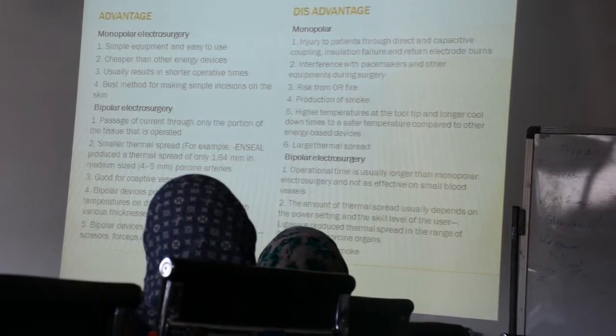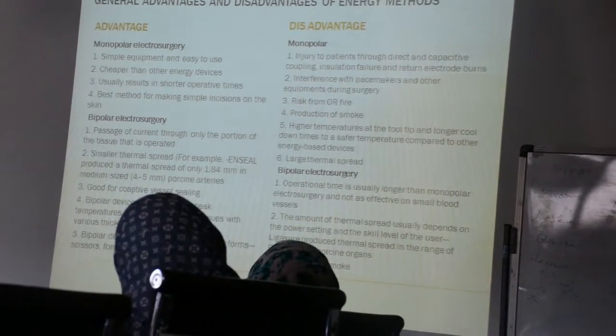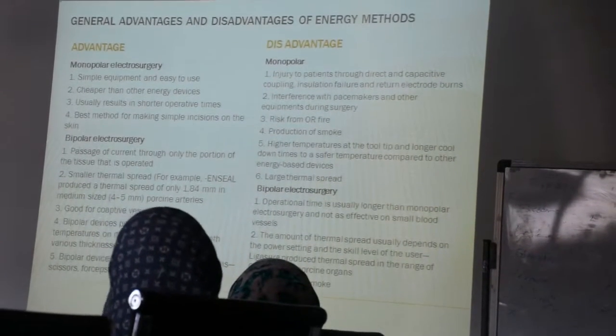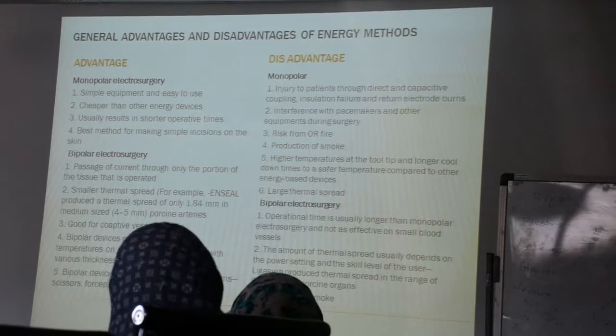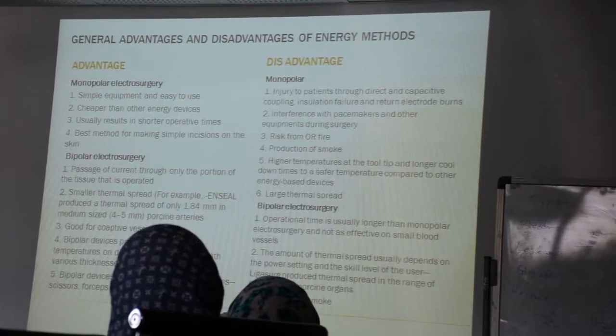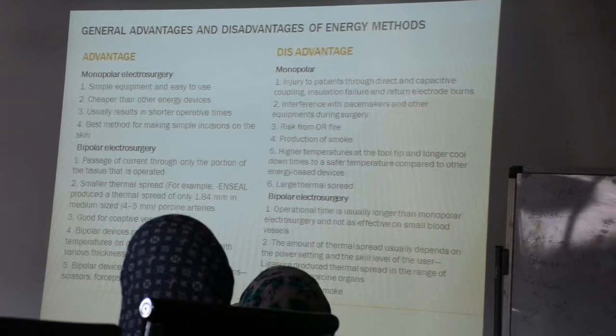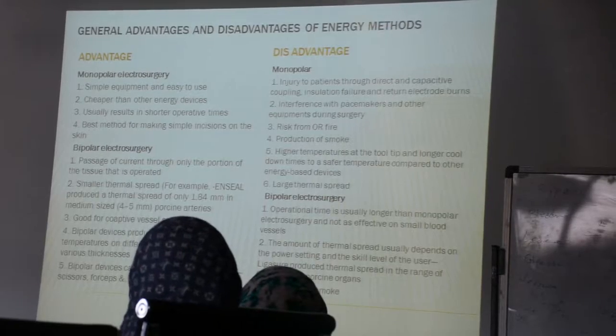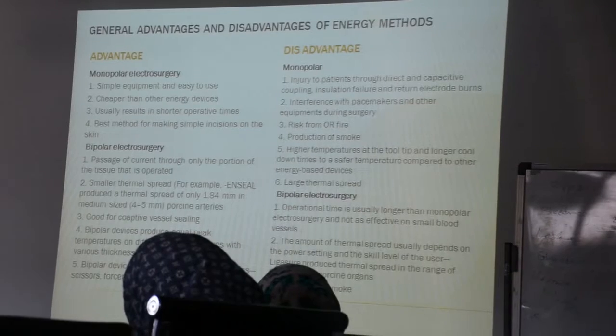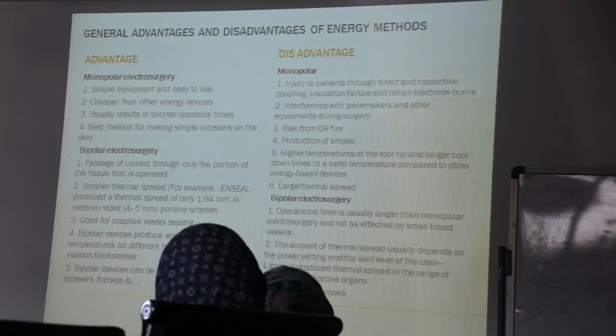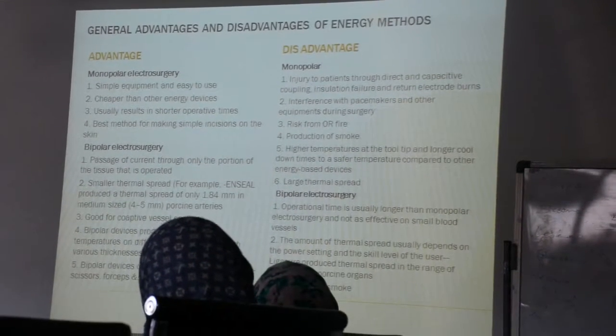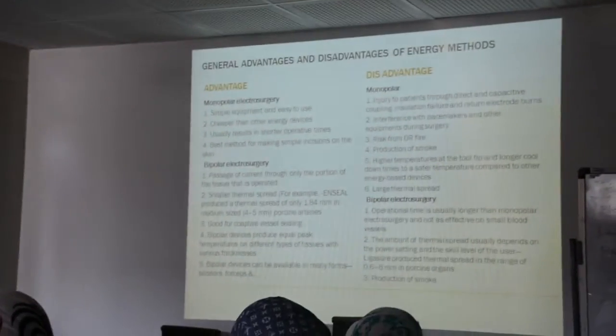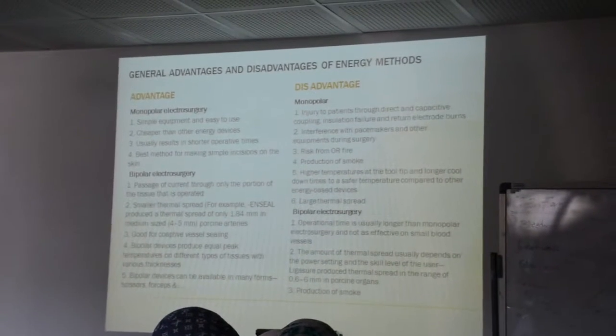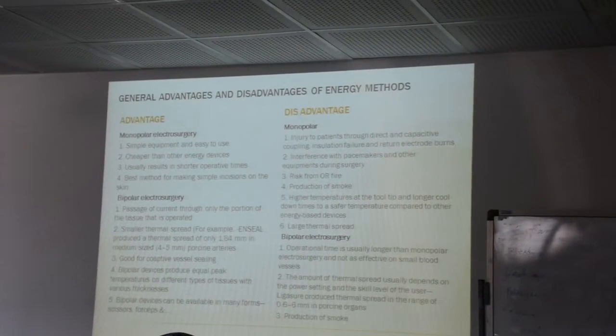Large thermal spread. Bipolar electrosurgery. Advantages of bipolar electrosurgery: passage of current through only the portion of the tissue that is operated. A small thermal spread, for example, produces a thermal spread of only 1.84 mm in a medium-size, 4 to 5 mm porcine artery. Good for sealing vessels. Bipolar devices produce equal peak temperature on different types of tissue with various thickness, small blood vessels. The amount of thermal spread usually depends on the power setting and the skill level of the user. Ligature produces thermal spread in the range of 0.6 to 6 millimeters in porcine organs.